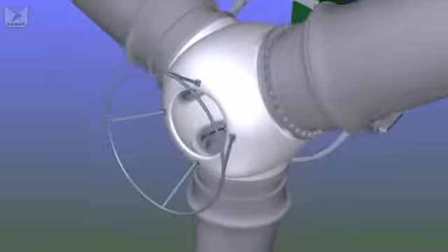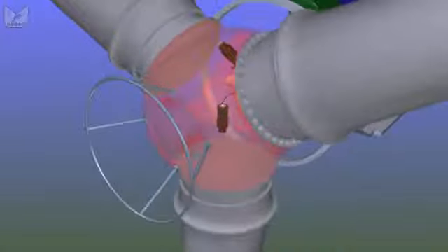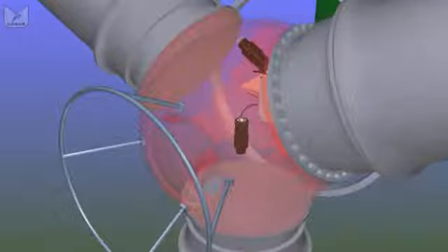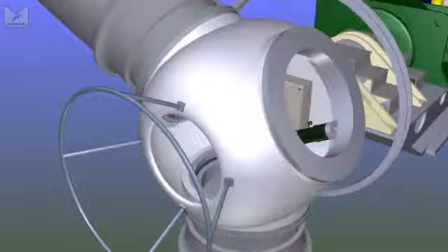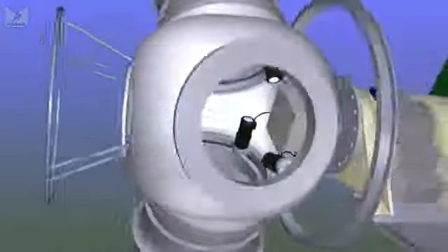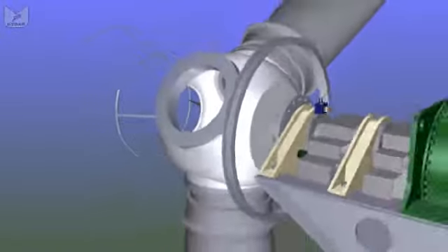It's a bit of a wriggle, but you wriggle through, usually feet first, crawl through the hole in the middle of the hub, and inside the hub we'll find the control electronics, the pumps, the motors and the batteries to control the pitch of each blade, rotating it on its own bearing to set the optimum angle for the wind. If we turn the blades through 90 degrees so they edge onto the wind, there's no net turning force. It's a process called feathering, and the turbine will stop.